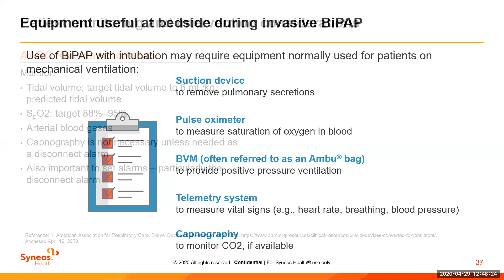So the American Association for Respiratory Care, when ventilators came in short supply, came out with recommendations for BiPAP use, as well as many state boards. What we want to do with ventilator support is target the tidal volume to 4 to 8, or 6 mLs per kilogram of ideal body weight or predicted body weight. We've been over these a little bit with the target goals for mechanical ventilation. Saturation is 88 to 95%. We monitor arterial blood gases for CO2 and pH. Capnography is not necessary, but if you have it, it's an outstanding disconnect alarm. It is your first source of disconnect alarm, better than the ventilator even. Hit next, we'll bring up the other considerations.